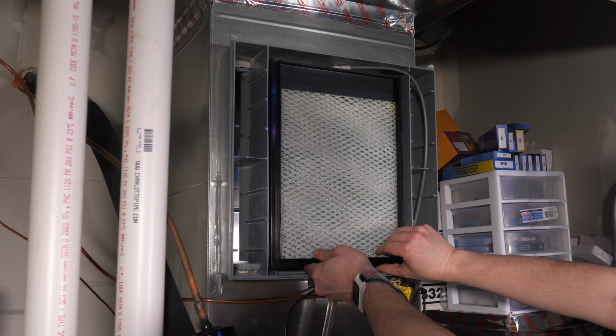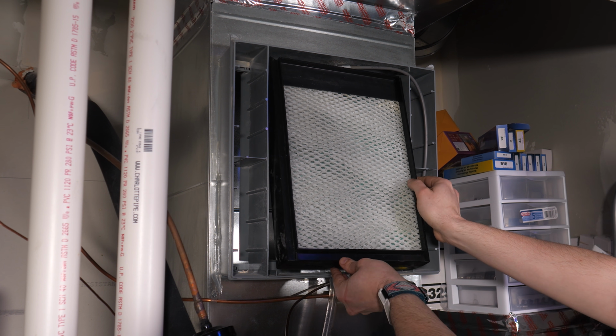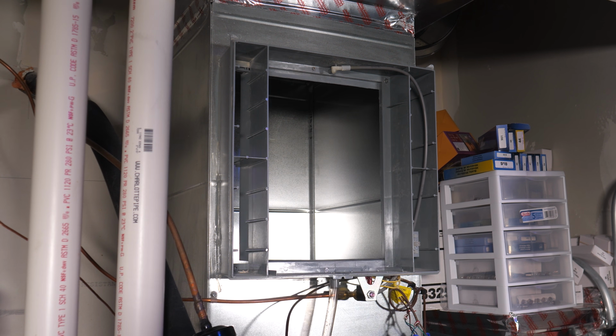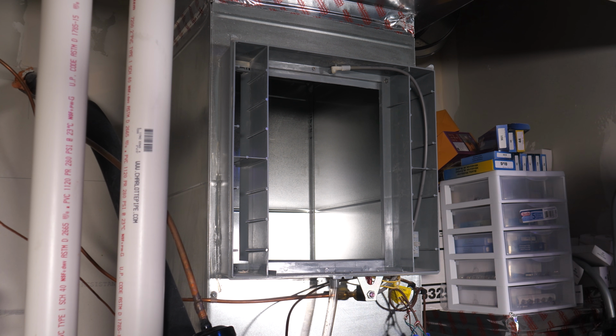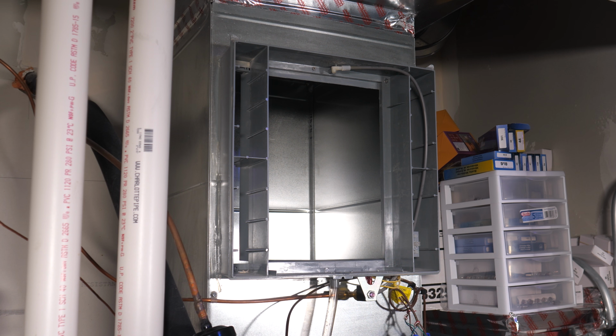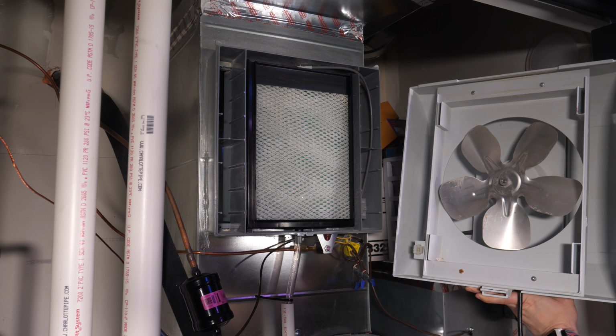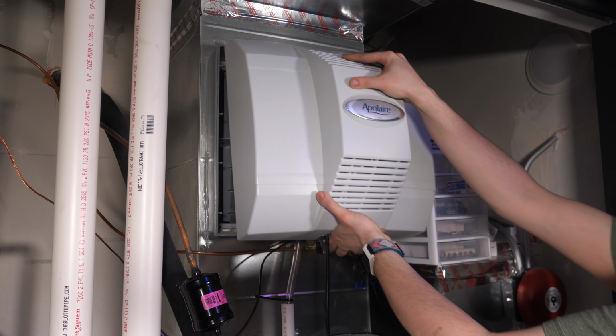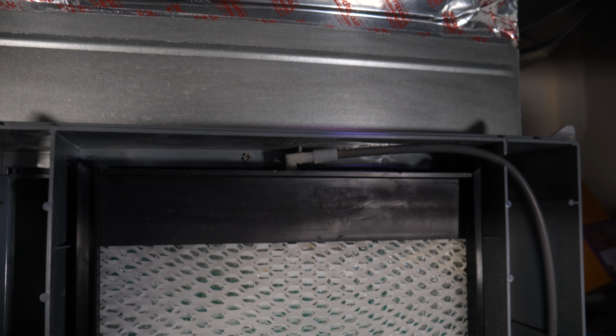If it's running during a heating call, the air the humidifier is taking from the furnace and blowing past the pad will be hot, which will help water to evaporate. But if it's running during a fan call, that air is only at room temperature, and the water won't evaporate as quickly. Honestly though, I have a hunch it would actually work fine if it were hooked up to cold water, and the real reason they want it hooked to hot water is to minimize the cooling which would occur as water evaporates. This thing is basically a swamp cooler, and it will drop the temperature of the air leaving the vents if it's running, but if the pad is soaked in hot water, that cooling effect is diminished somewhat and possibly even eliminated. But anyway, that's not important.